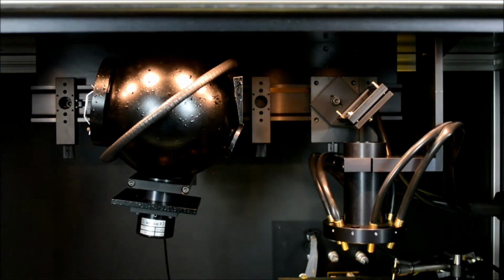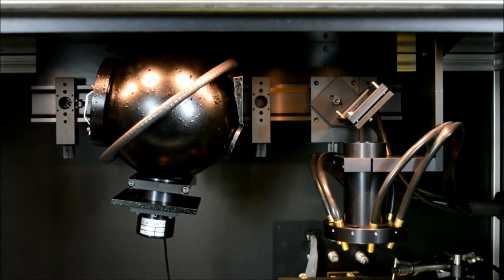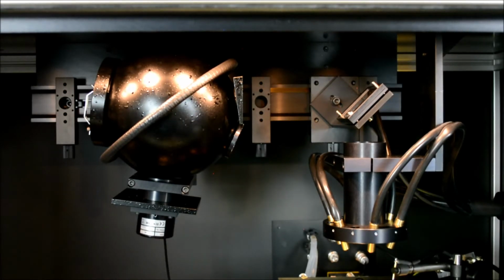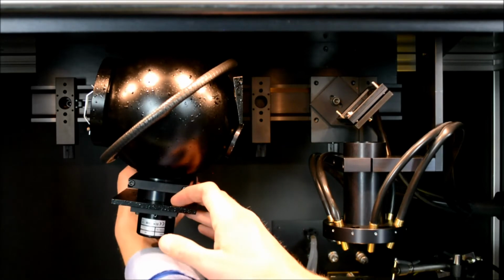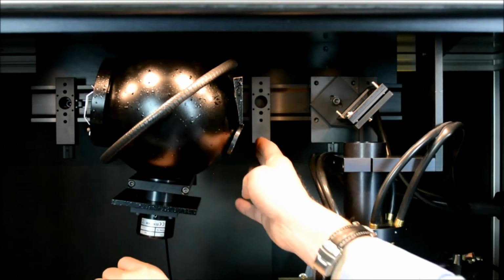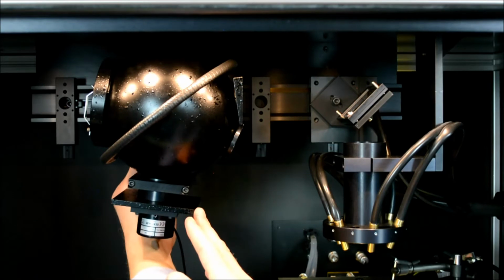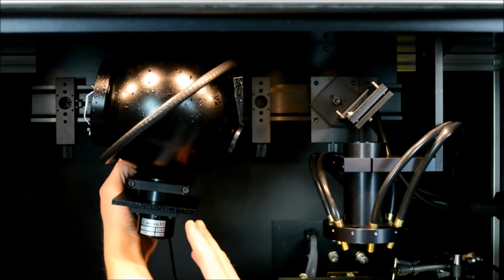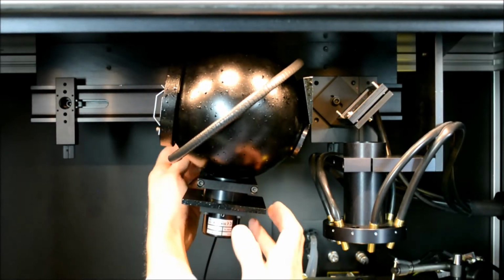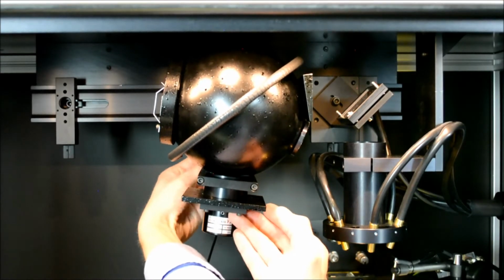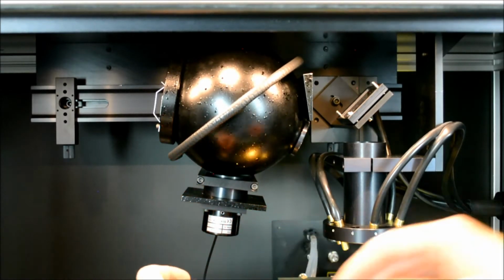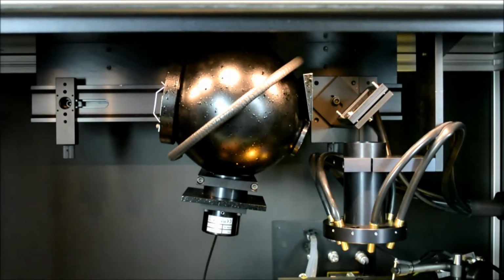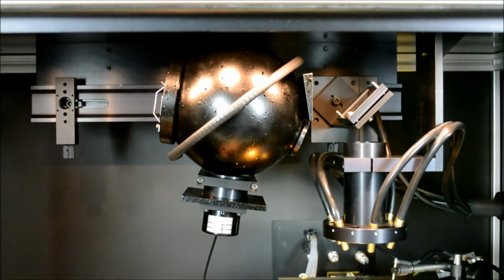For the measurement of spectral reflectance, we will use as sample the monocrystalline silicon sample, which we have measured in EQE spectral responsivity previously. The DTR6 for the measurement of reflectance should be moved to the right-hand stop. One loosens the carrier of the sphere by a quarter of a turn, pushes to the right-hand stop, and locks in place. In this manner, the beam of the TMC 300 is focused at the plane of the reflectance port.